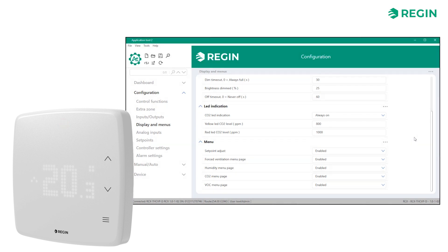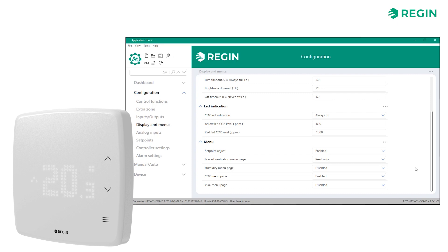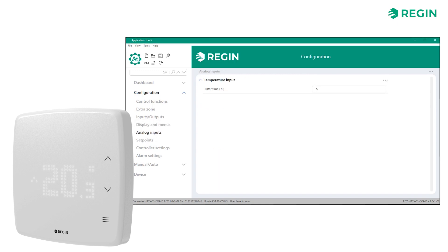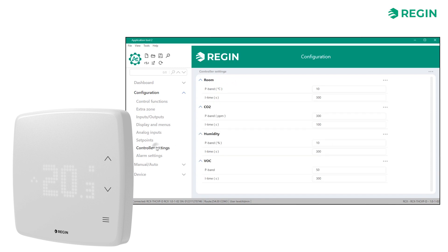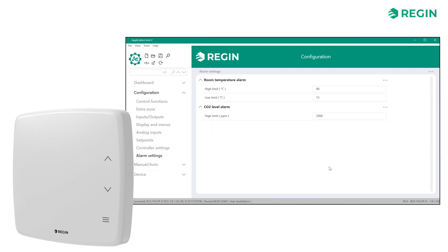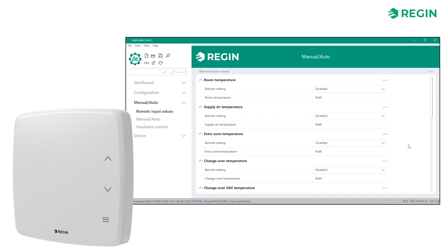Finally, we can enable or disable the different menu items available on the display. For this example, let's enable set point adjust and the CO2 menu page, but set the remaining items to disabled or read-only to make them viewable but not adjustable. Under analog inputs, we can adjust the filter time for sensors. Under controller settings, we can set values for P-band and I-time. Alarm settings makes it possible to adjust alarm levels when communicating to a central SCADA system. The next three sections are grouped as Manual/Auto and allow for manual control. Under remote input values, you can set your own values to override actual values — useful for testing a configuration.